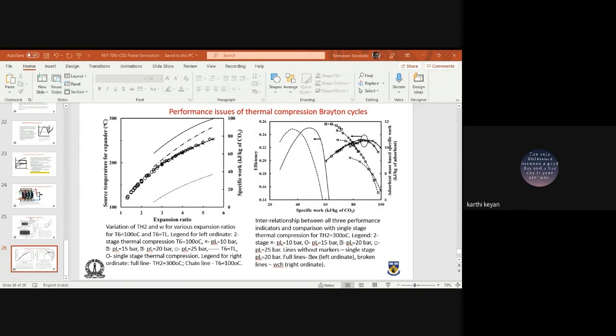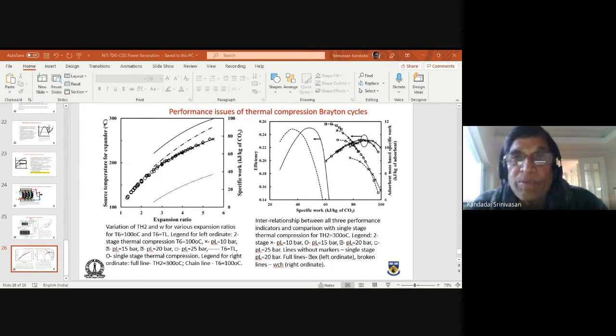But regarding cascade refrigeration, people only focus on R744 and R717. Instead of that, we can use ethane and propylene. Propylene can be used, but they are actually used in the LNG industry, where you require extremely low temperature. LNG has to be liquefied pretty close to about minus 150 degrees or something like that.